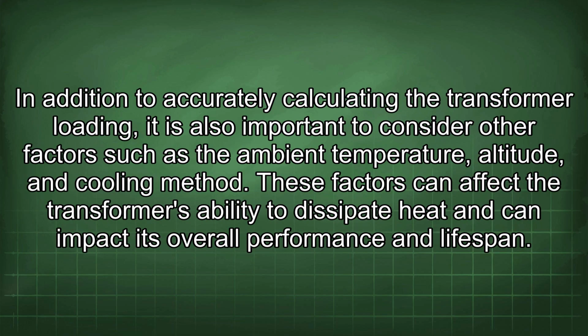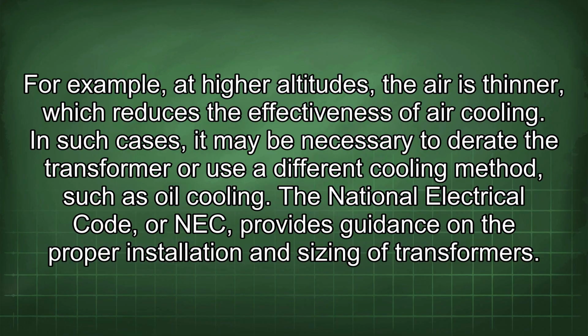In addition to accurately calculating the transformer loading, it is also important to consider other factors such as the ambient temperature, altitude, and cooling method. These factors can affect the transformer's ability to dissipate heat and can impact its overall performance and lifespan. For example, at higher altitudes, the air is thinner, which reduces the effectiveness of air cooling.